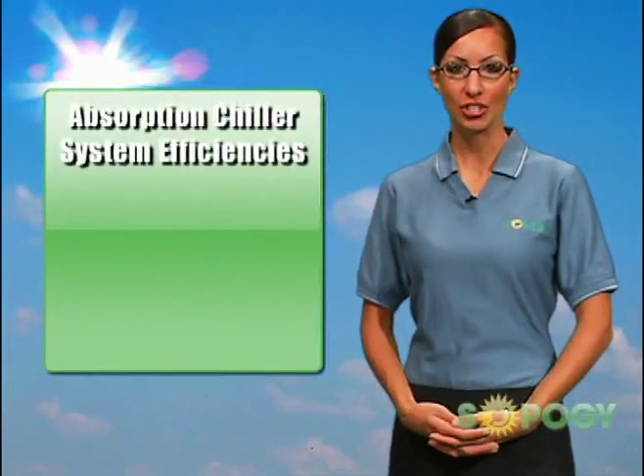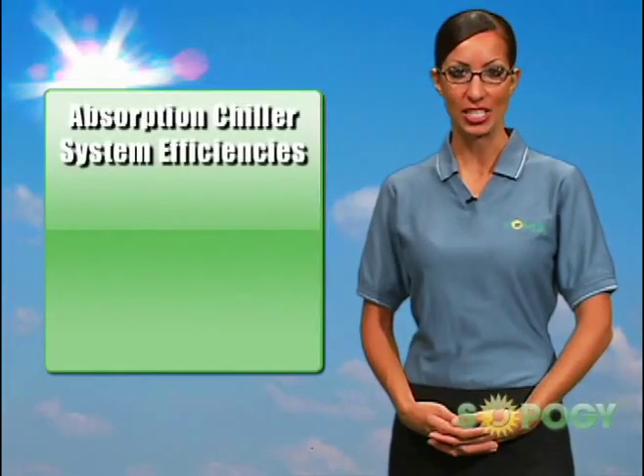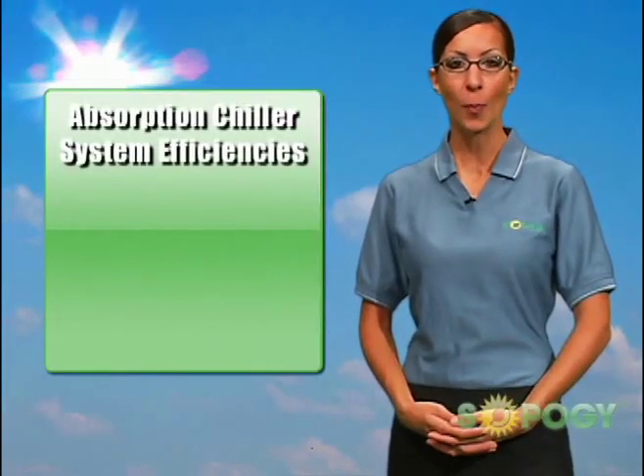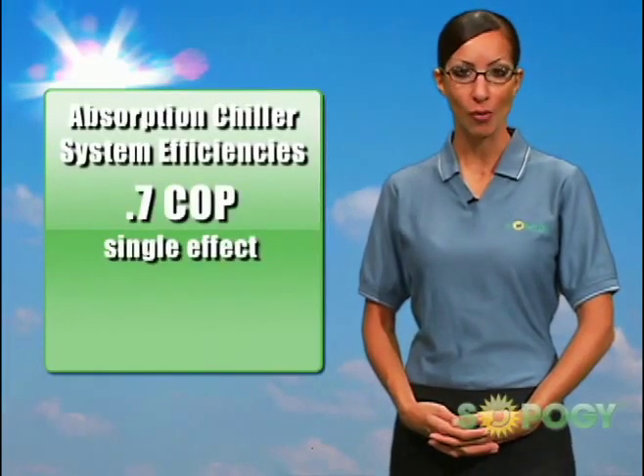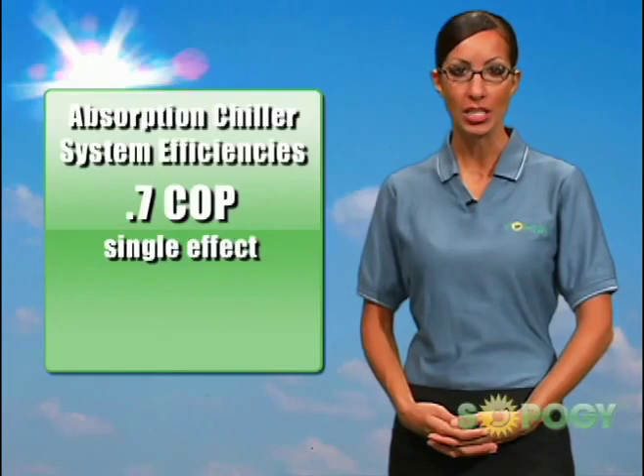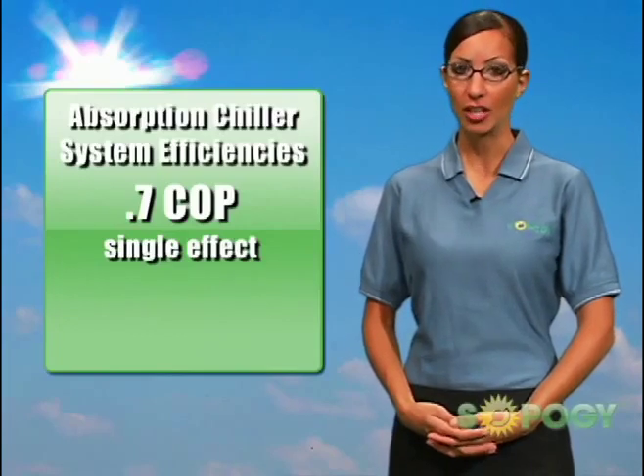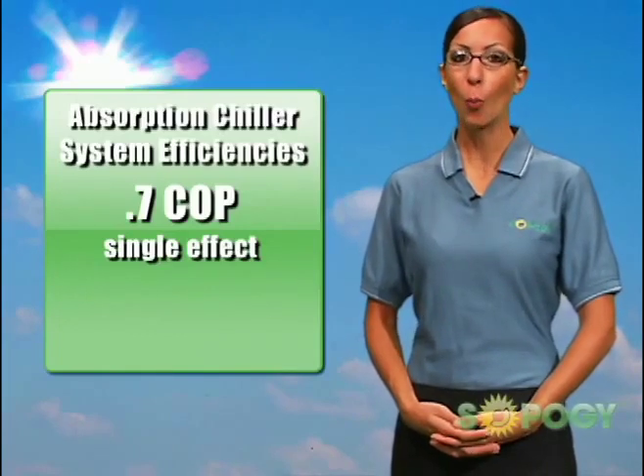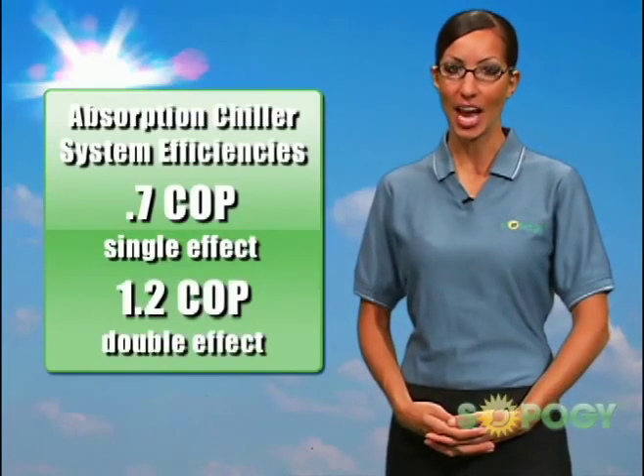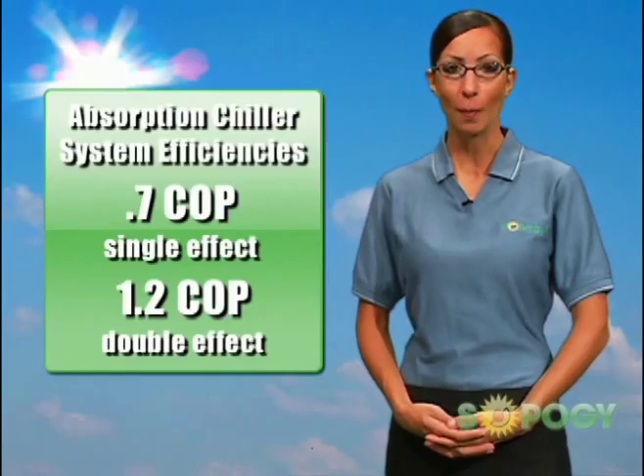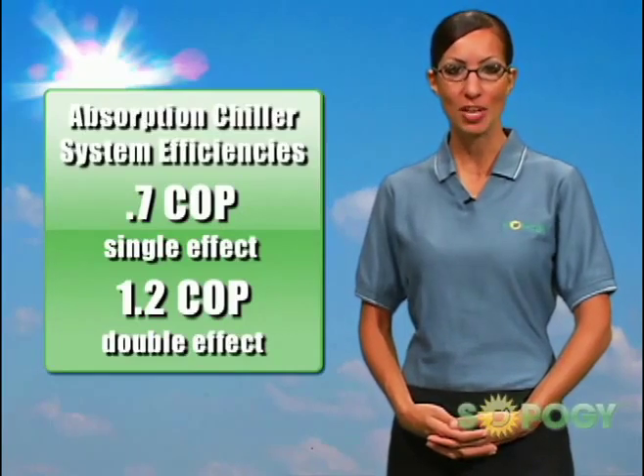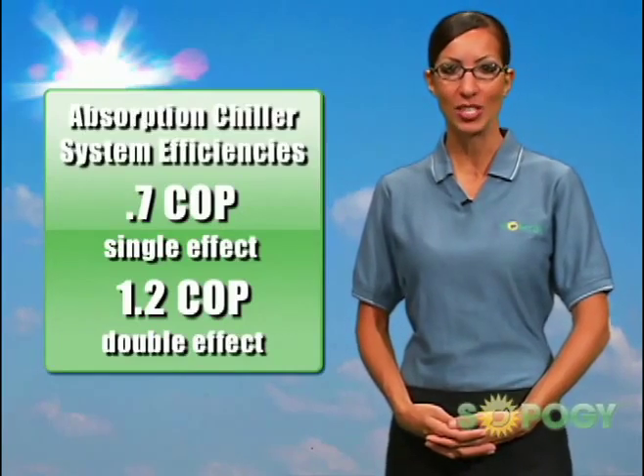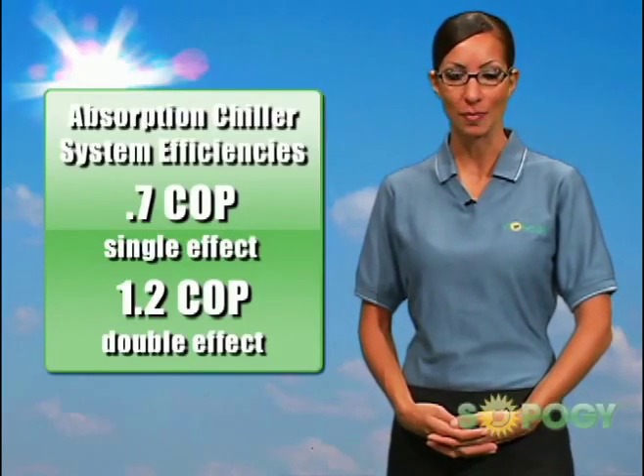Absorption chiller system efficiencies are often around 0.7 COP, or coefficient of performance, for a single effect, or 1.2 for a double effect absorption chiller, making for a good complement to the efficient SOPOGY micro-CSP solar collector.